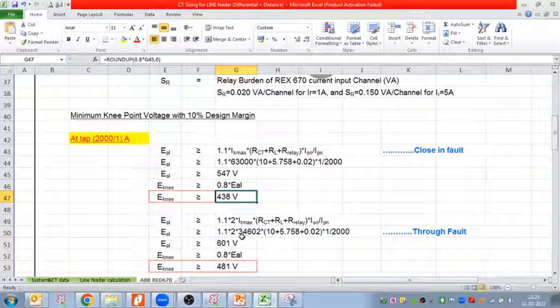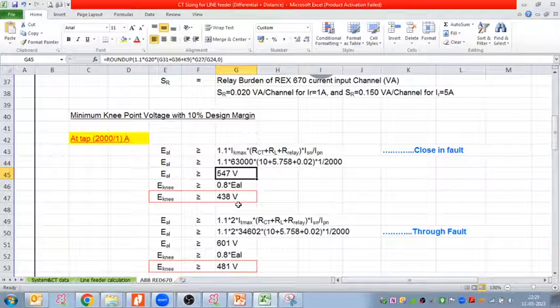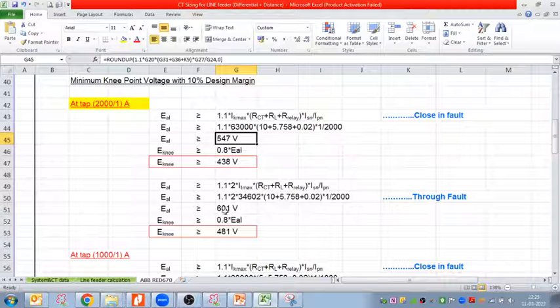But for the better case, do not take 438, do not take 547. You go with, like here, we have already done the 1.1 margin. So it is better to keep 600 voltage or 700 or 800 voltage. That would be better. Anyway, this is what is exactly required, the minimum required by the relay.